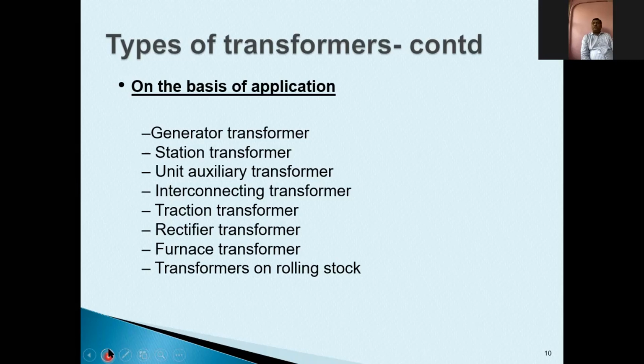When I'm talking about generator transformer, the voltage ratio is very high. I'm generating at 22 kV or 21.6 kV and I'm transmitting this to 400 kV directly from the generation plant. So the transformation ratio is almost 20. And also, you see, what is the capacity of the generation plant? Each machine today has a capacity of 500 megawatt or 800 megawatt in supercritical thermal plants. So this 800 megawatt machine may need a 1000 MVA transformer. Can you imagine the ampere rating of this 1000 MVA transformer at 22 kV? We are engineers, we can calculate it. So it may be somewhere around 25,000 amperes.